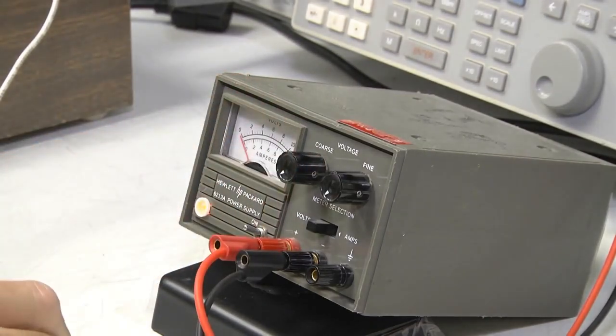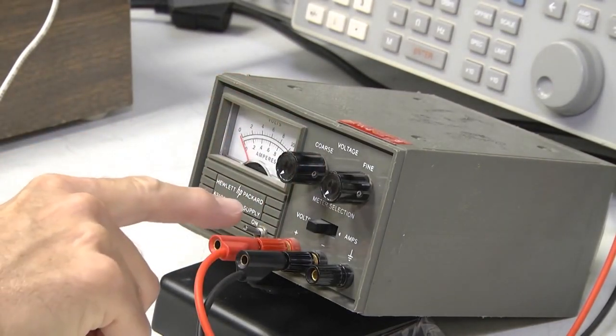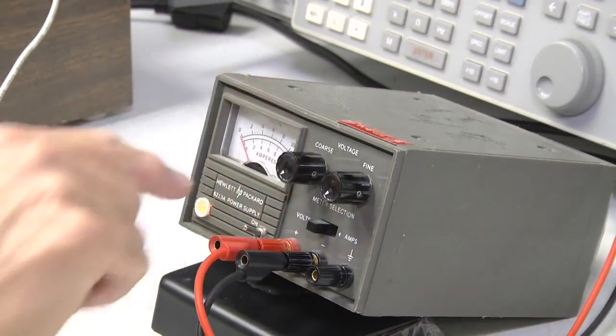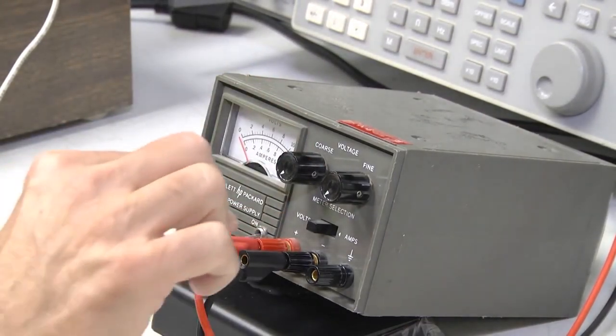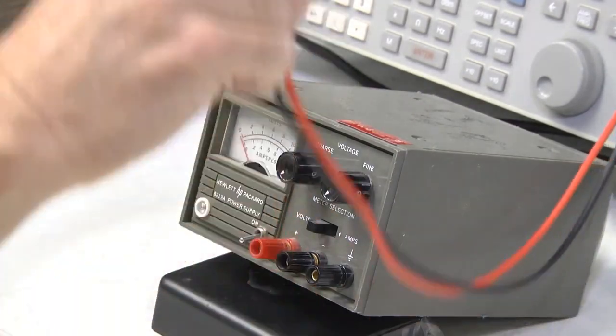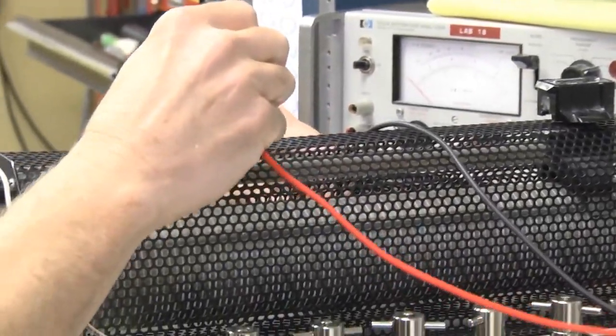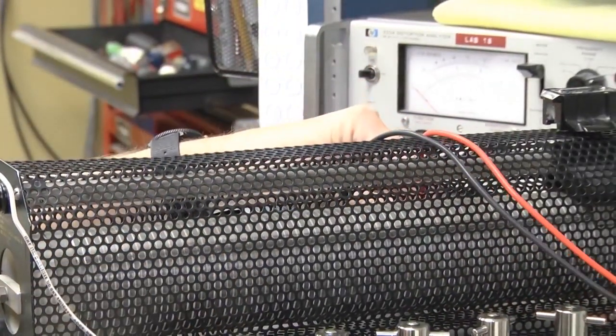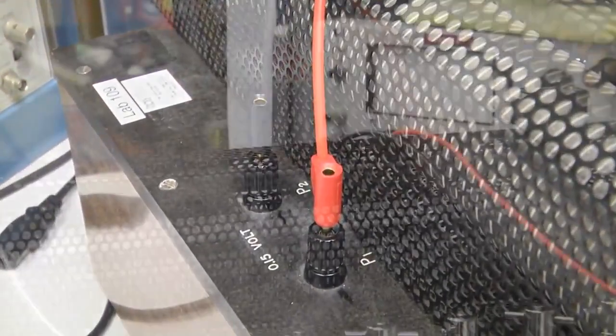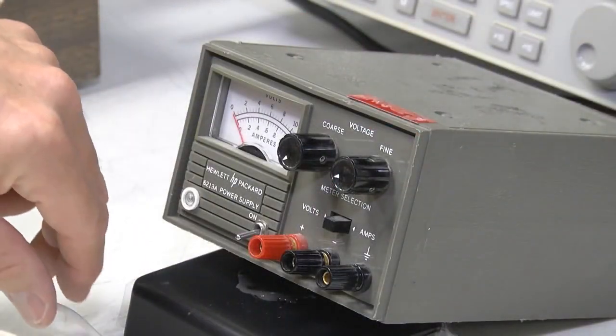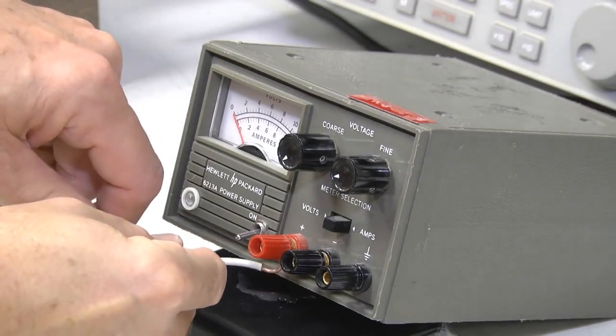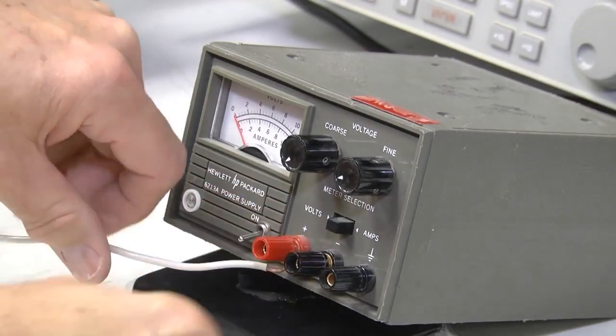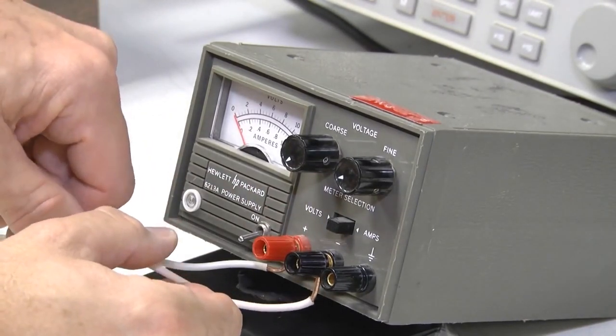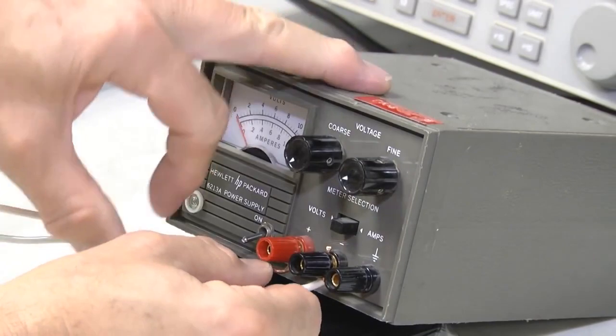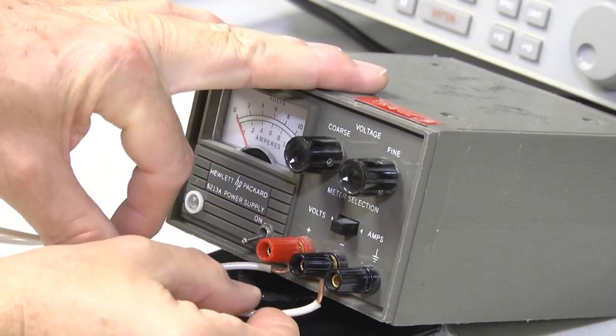The next procedure that we're going to do is check the calibration of the current meter on the HP power supply. So we'll turn the voltage down, turn the unit off, and we'll disconnect the digital multimeter from the power supply, and we'll move the test leads to the output of the Guildline current shunt so that we can measure the voltage across the shunt on the digital multimeter. To calibrate the current meter portion of the HP power supply, we go ahead and connect the current shunt and its load resistors using solid copper wire to the front panel output of the HP power supply.